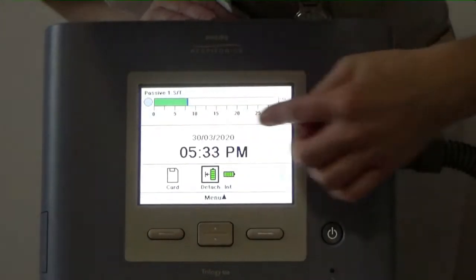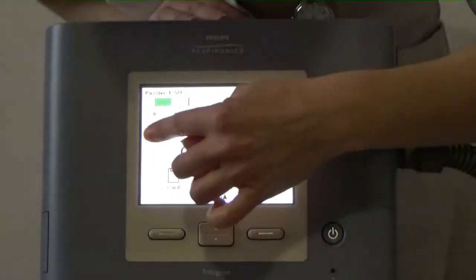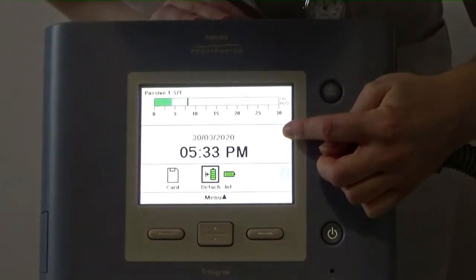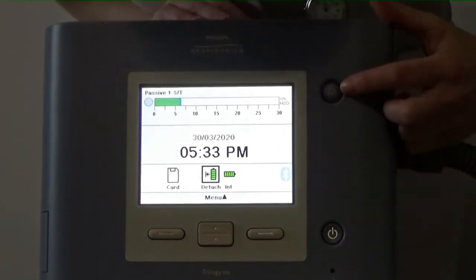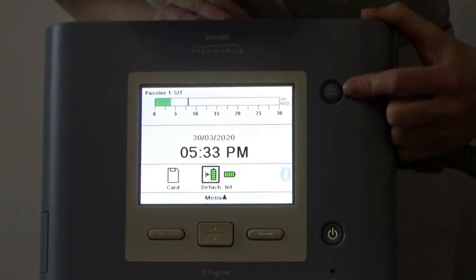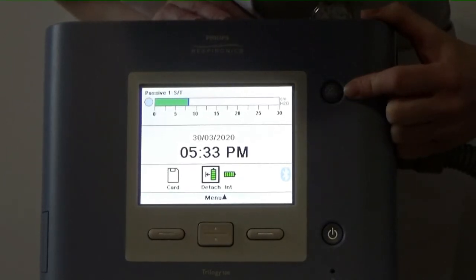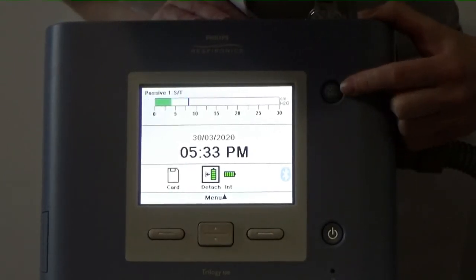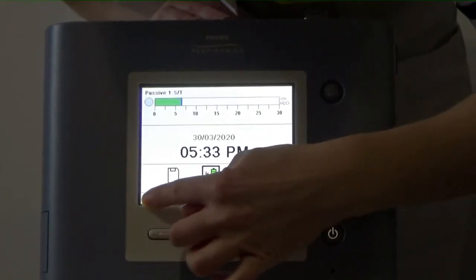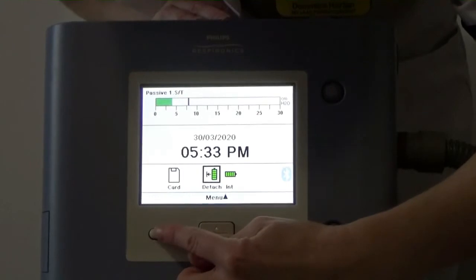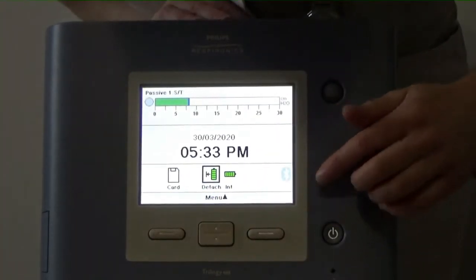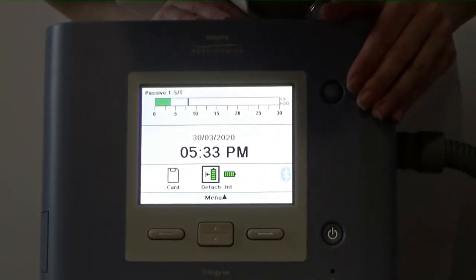Now, if you do have any alarms go off on your machine, there'll be a red or a yellow bar that shows with an alarm message. This button here will give you 2 minutes of silence whilst you sort out the issue. Once you've figured out what's going on with the device and you've sorted it out, there'll be a button here which says reset. Press here and that will accept the alarm and go back to usual ventilation again.